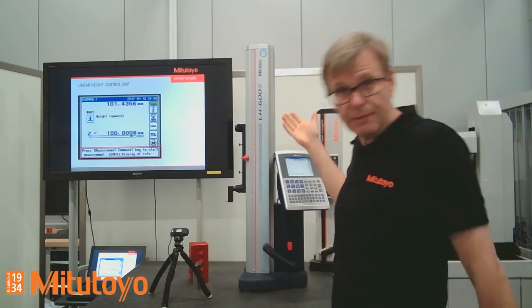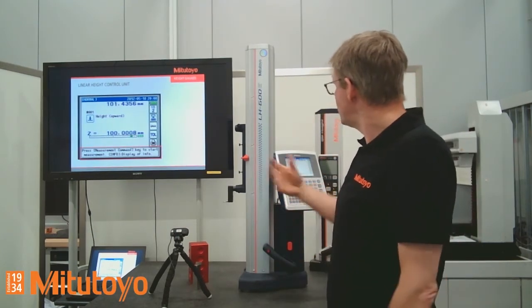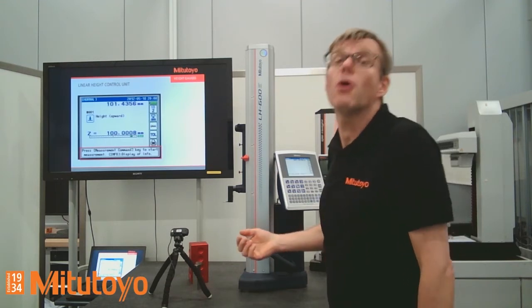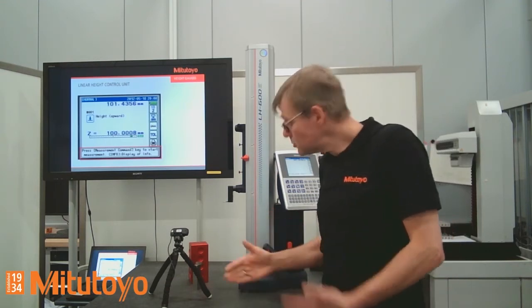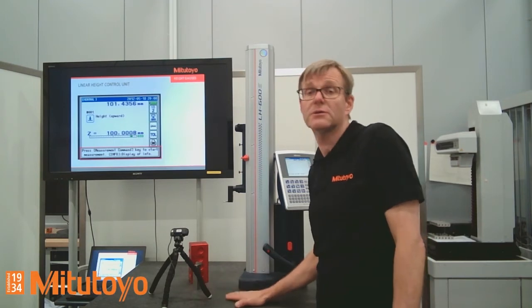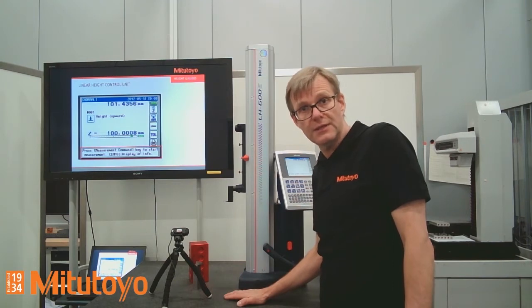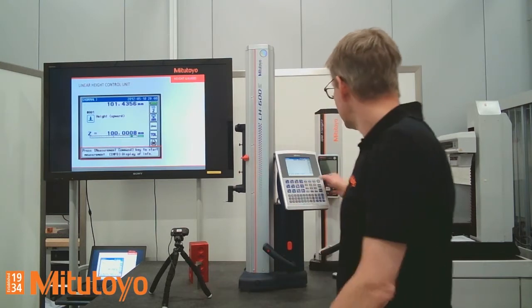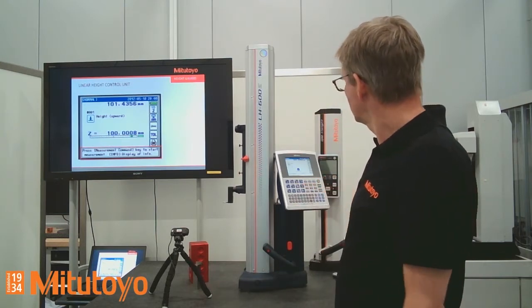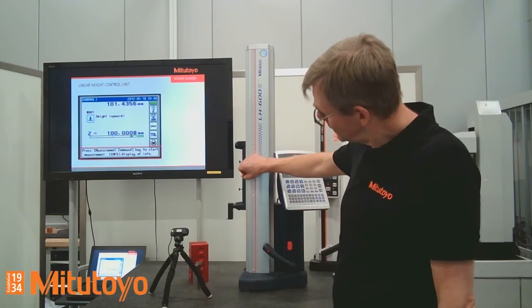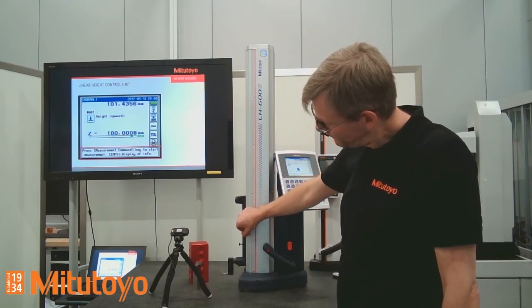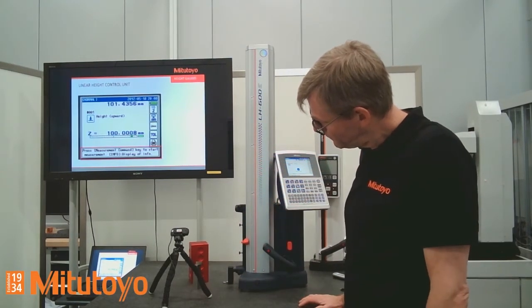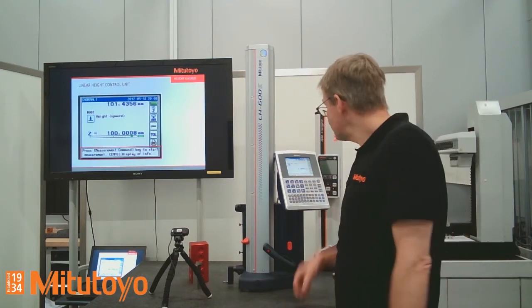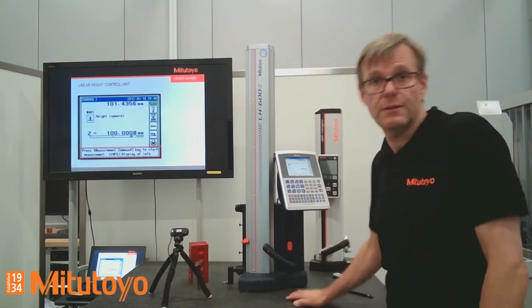But first of all, I switched on the machine. Yeah, and the first step is to set the zero point, origin point. So it could be on the granite plate, and usually it's on the granite plate. So this is our reference point, our reference plane. So that means I would like to put 0 point on the granite plate, origin point. So let's do this. And then you can see the machine is moving. That's it. Now we have the 0 point on the granite plate.